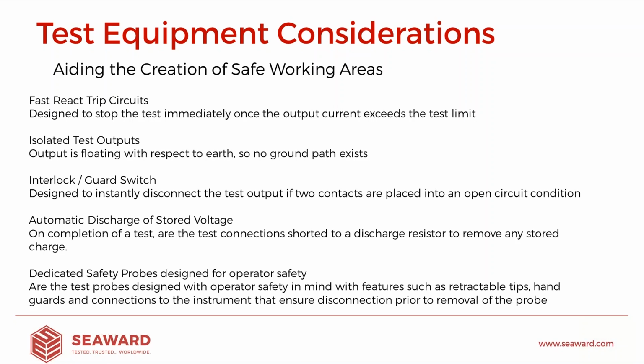I would always recommend looking for a hardware-driven solution for this rather than something in software where you can switch it on and off, because we do then potentially look for a fault condition where the software fails and doesn't open the interlock. So the Seaward products are always developed with a hardware solution in mind. So it is a very, very simple hardware short circuit. If that doesn't exist, testing isn't allowed to go underway. So this can be linked to many ways.